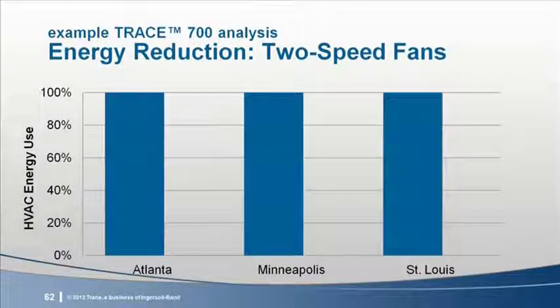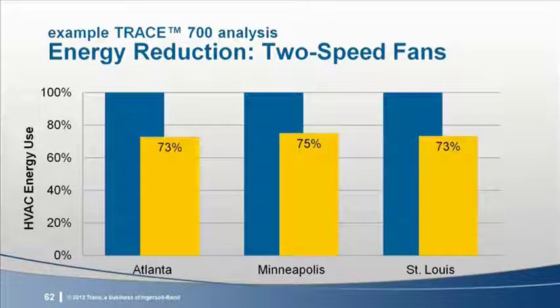Each city is represented with a baseline model marked in blue. The yellow bars show the system energy usage for single-zone VAV systems with two-speed fans. In this instance, the two-speed fans operate at design airflow when the system is heating. The results show potential to save energy by employing single-zone VAV systems even with two-speed fans. Remember that two-speed fans are the minimum defined by standard 90.1.